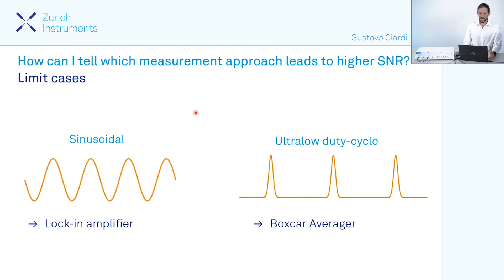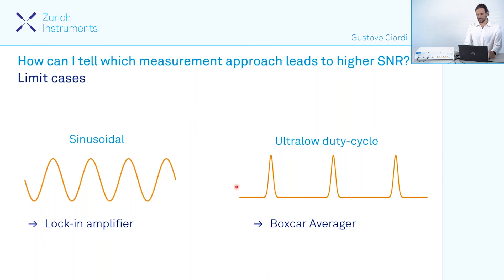How can I tell which measurement approach leads to the best SNR for my experiment? Is there a recipe for this? For limit cases we can say that if we have a signal that is basically purely sinusoidal, I would like to measure my signal with the lock-in amplifier. At the same time, if I have a signal whose duty cycle is ultra low, the boxcar averager will be the best choice.